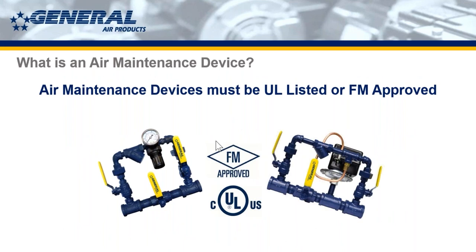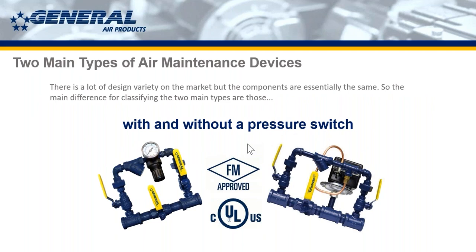So the first thing that makes this series of pipes, nipples, valves, etc., an air maintenance device is its UL or FM listing or FM approval. So to be an air maintenance device, it must be listed or approved. That said, you'll see there's a lot of companies that make an air maintenance device. There's probably close to 8 or 10 on the market at this point. And with those comes a variety of designs, but they're essentially working the same. And you can break those designs down into two main types, and that's with or without a pressure switch. As you can see, the air maintenance device on the right is an air maintenance device with a pressure switch. And we're going to talk about what the differences there are more specifically.